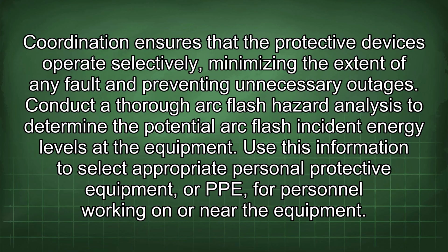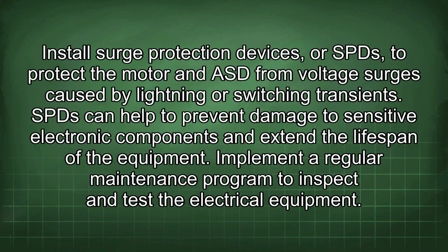Conduct a thorough arc flash hazard analysis to determine the potential arc flash incident energy levels of the equipment. Use this information to select appropriate personal protective equipment, or PPE, for personnel working on or near the equipment. Install surge protection devices, or SPDs, to protect the motor and ASD from voltage surges caused by lightning or switching transients. SPDs can help to prevent damage to sensitive electronic components and extend the lifespan of the equipment.